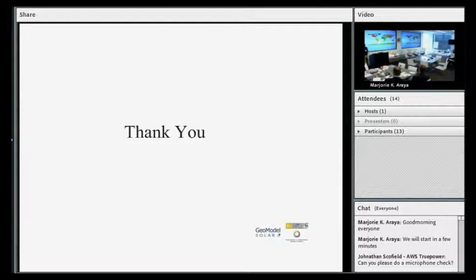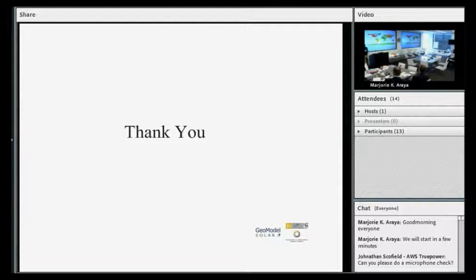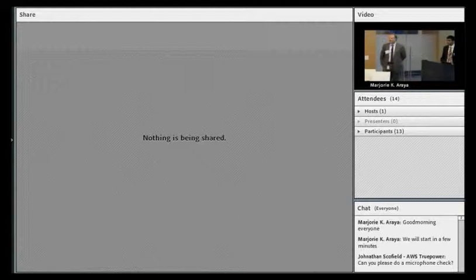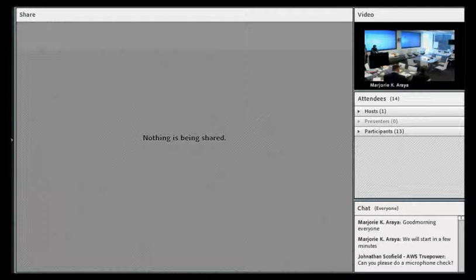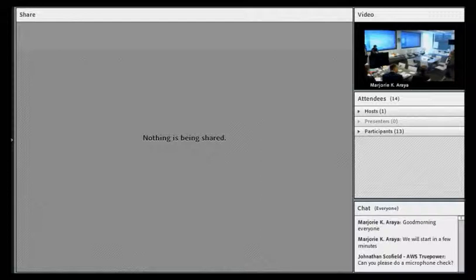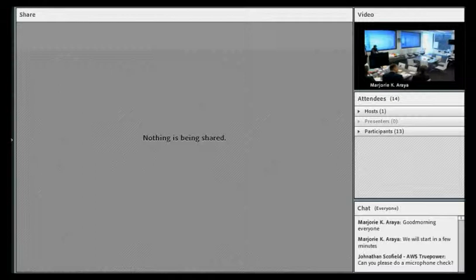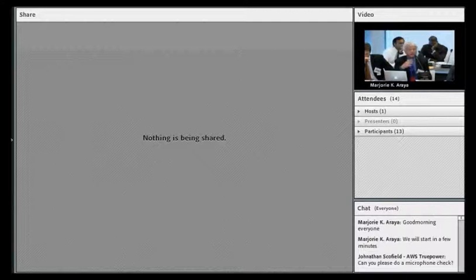Thank you very much. So we've got a couple of minutes available. Any questions that you might have for the two gentlemen? I just wanted to emphasize the point that you were already making about the solar measurements and it's also in order to achieve the kind of accuracies you're talking about there. It's also essential that a calibration program be established within the country where the instruments are traceable back to the world radiometric reference every few years because these instruments do drift over time. The calibration factor does drift so you're not going to have that same accuracy unless you maintain some kind of an ongoing calibration activity. Good. Thank you.